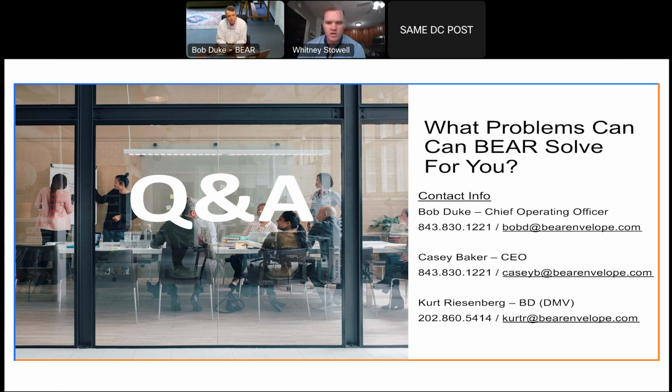We have a question in from Caroline Wang. Caroline asks, what are the fire protection considerations for envelope products? There are two considerations. First of all, if you wanted to take an additional step, you can seal it with foam and then put mineral wool on top of it, which is a fireproofing material. Or they do make such a thing, it's called fire foam. And fire foam is created for both fire stop and those 1-hour firewall areas. The foam you saw in the presentation today was white in color. Fire foam is typically orange in color to match the orange fire caulk that you typically see on a wall.